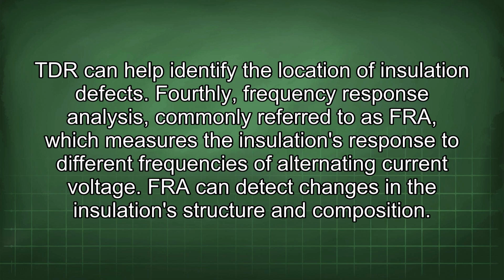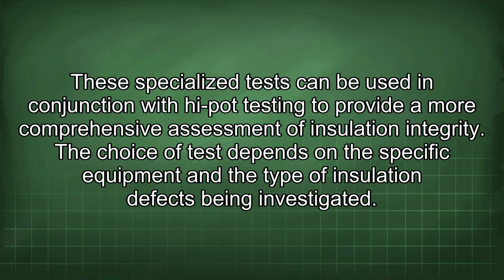Fourthly, frequency response analysis, commonly referred to as FRA, which measures the insulation's response to different frequencies of alternating current voltage. FRA can detect changes in the insulation's structure and composition. These specialized tests can be used in conjunction with high-pot testing to provide a more comprehensive assessment of insulation integrity. The choice of test depends on the specific equipment and the type of insulation defects being investigated.